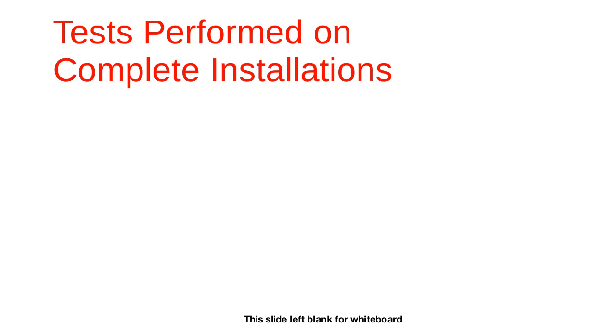That's why we say the installer, the electrician installer or the engineer, should be the one to conduct these tests and inspection, because they'll be able to ascertain, like the tightness of the connections, and that installer should be inspecting that work. That column also should inherently be carried out by the installing operative and completed on the inspection checklist paperwork and passed to the test engineer if this is a separate individual, which we discouraged. We said it is important that the installer remains also as the test engineer, unless he's a semi-skilled worker and not an approved engineer.